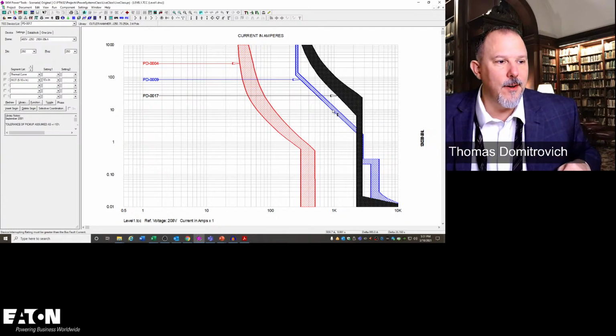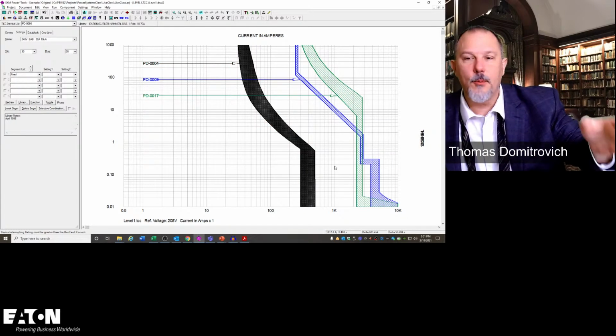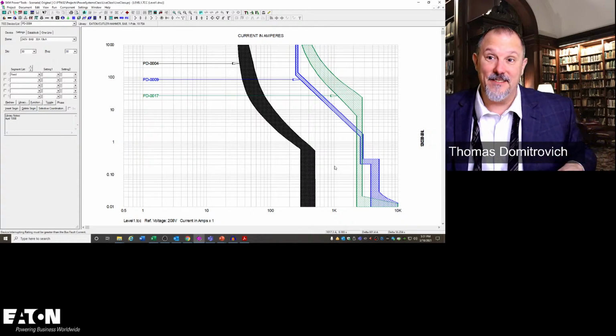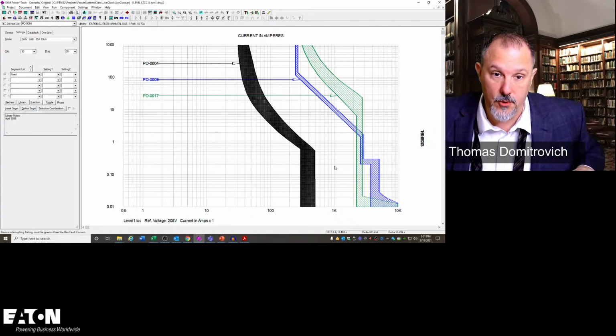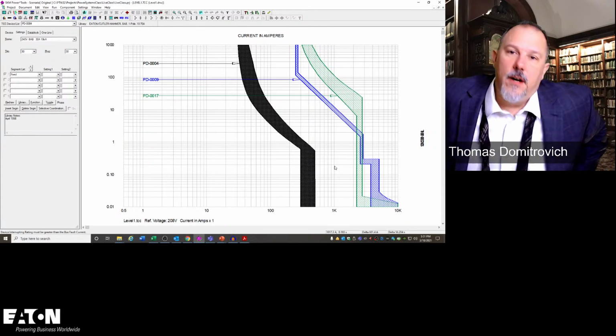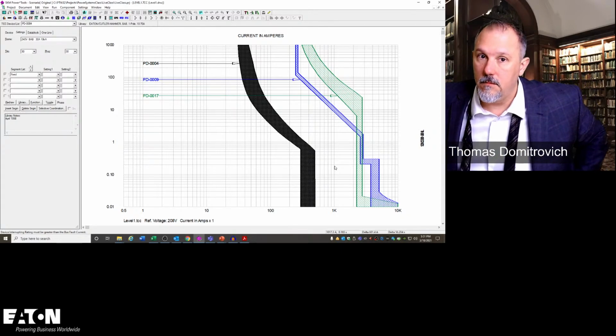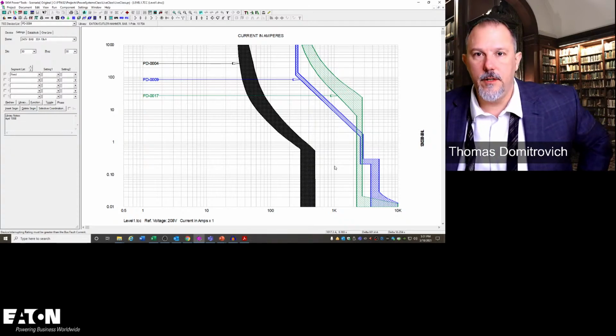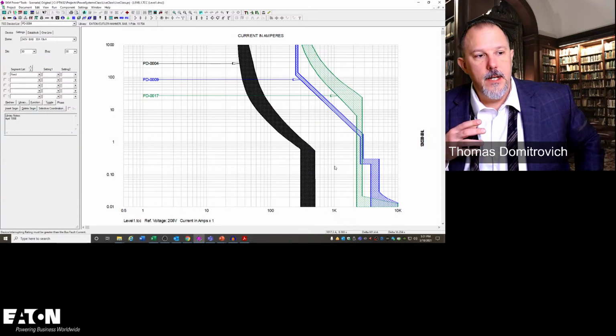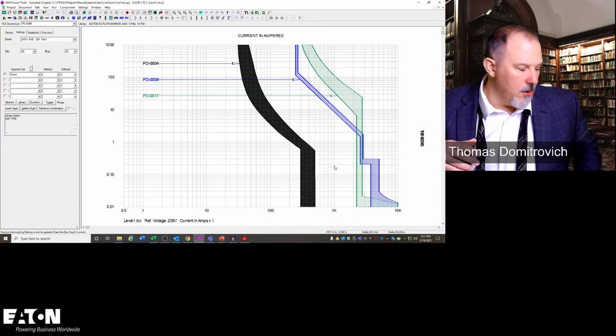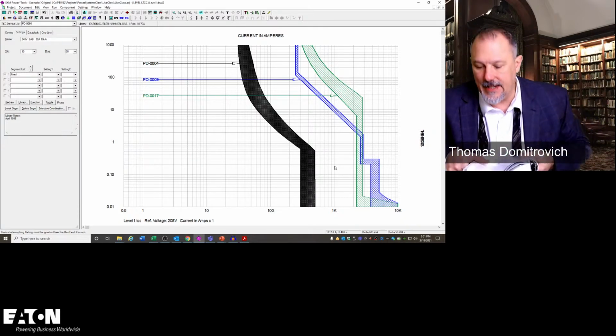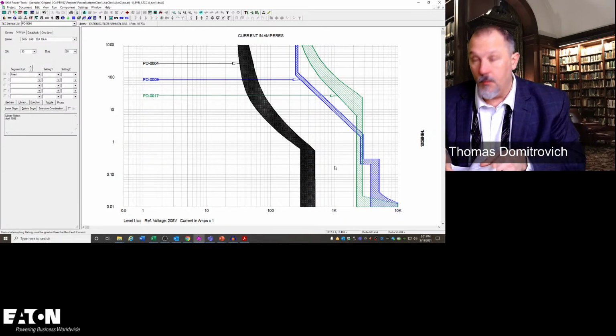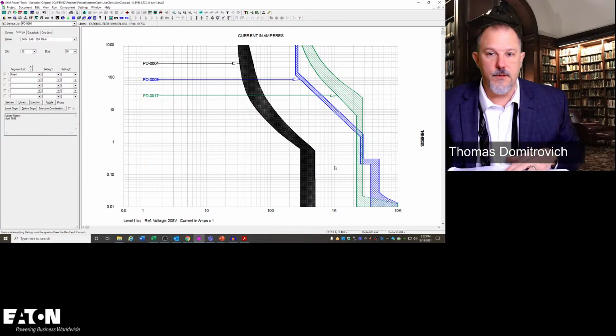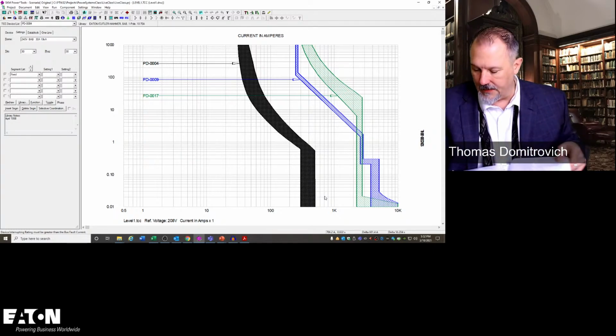Now, you'll say, well, heck, with that BAB breaker, I've got separation all the way down to 0.01 seconds. Right, for you 0.1 second gurus, I'm not going to make fun. I am going to keep it civil. We're going to focus on technical, right? So, 0.1 seconds. If you look in 517, Article 517 introduced 0.1 seconds. Now, if I had these two curves right here, you tell me, if you're brave enough, do these curves selectively coordinate?